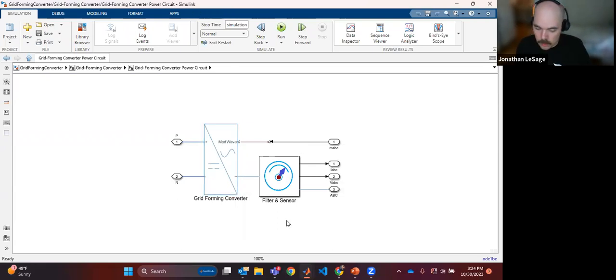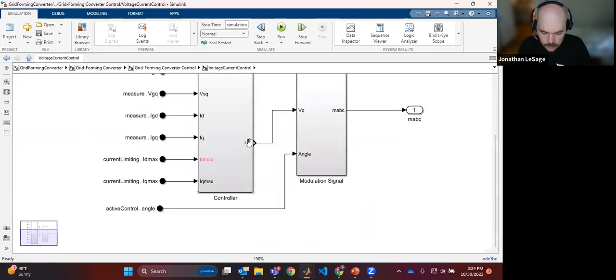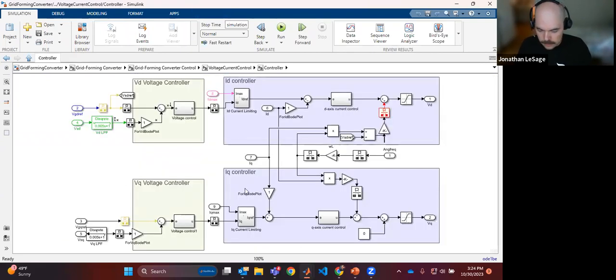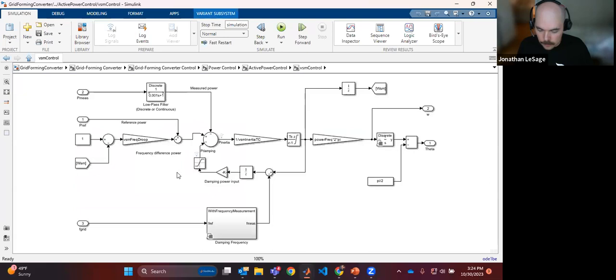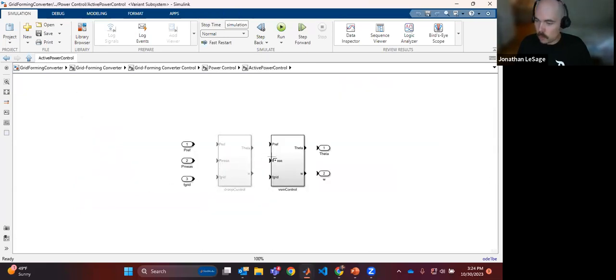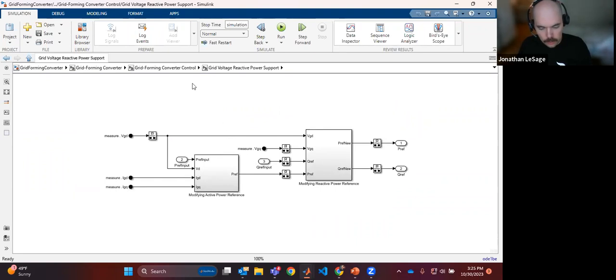On the control side, I've got a hierarchical control structure with lower-level control — d and q axis control — and then higher-level reactive and active power control. On the active power control, I have variants, so I have different control strategies that can be enabled: droop control and a VSM-type control as well. Lastly, there's a higher-level reactive power support control loop.